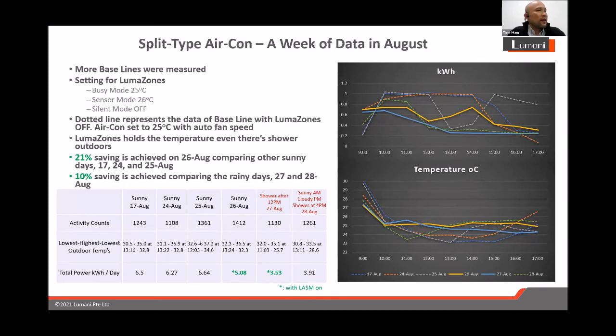This is what we save on the split type aircon in our office. It's only one zone, so it has no effect on the zoning, no saving on zoning. It's purely the temperature calibration and humidity control. You can tell that the dotted line is the original aircon control, and the yellow and blue lines are our LumaZone control. You can tell that it holds the temperature to 25 more closely than the original control. Therefore, it can save between 10 to 20%.